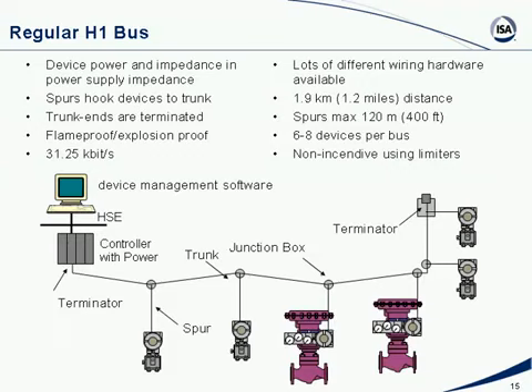We say that you can have 6 to 8 devices per bus. You can have as many as 16 devices per bus in most control systems, but there are other limiting factors. For example, each device consumes power. So along the bus, particularly if you have long wires, you get a voltage drop, and since each device needs 9 volts to operate, you can't have too long wires because there will be too little voltage available at the field end. Another limiting factor is the bus cycle time. If you put too many devices on the bus, it becomes too slow, and you would not be able to do control which is fast enough. For temperature, maybe you can put 16 devices because it's a slow process, but for flow and differential pressure, you're usually very fast, so you want to reduce the number of devices to get a fast response.